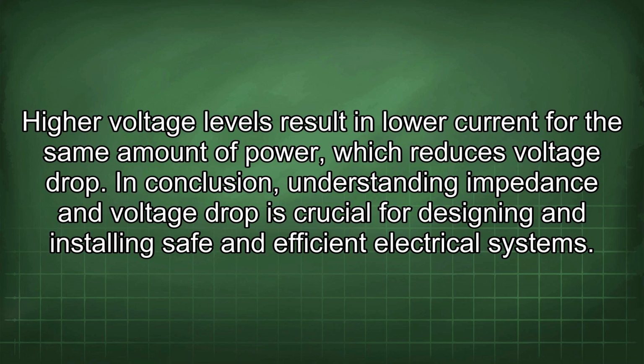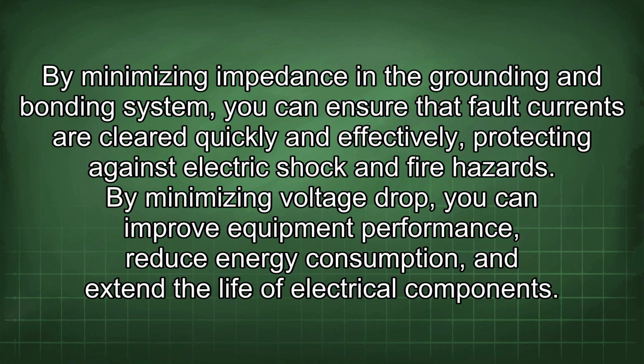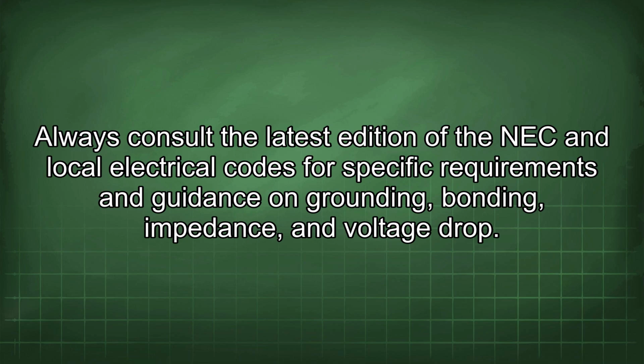In conclusion, understanding impedance and voltage drop is crucial for designing and installing safe and efficient electrical systems. By minimizing impedance in the grounding and bonding system, you can ensure that fault currents are cleared quickly and effectively, protecting against electric shock and fire hazards. By minimizing voltage drop, you can improve equipment performance, reduce energy consumption, and extend the life of electrical components. Always consult the latest edition of the NEC and local electrical codes for specific requirements and guidance on grounding, bonding, impedance, and voltage drop.